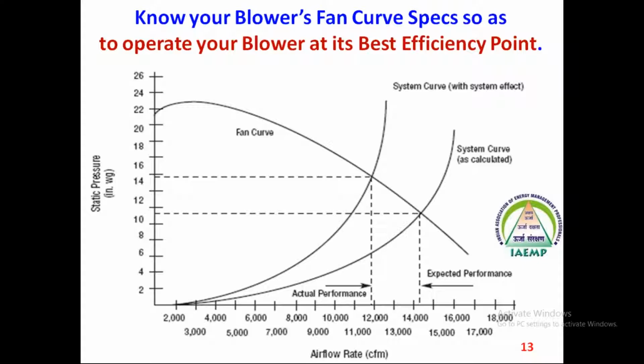narrowed ducts, put from end to end in the main plenum, from the main air conditioning chiller and blower to the end of the air conditioned premises. If there is a system resistance, automatically the static pressure increases, and ultimately instead of 14,000 CFM, it can deliver only 12,000 CFM at 14 inches water column. So ultimately this drop from 10 inches to 14 inches is there because of the static pressure drop across the filters. This is the area which can be done with IoT monitoring also.